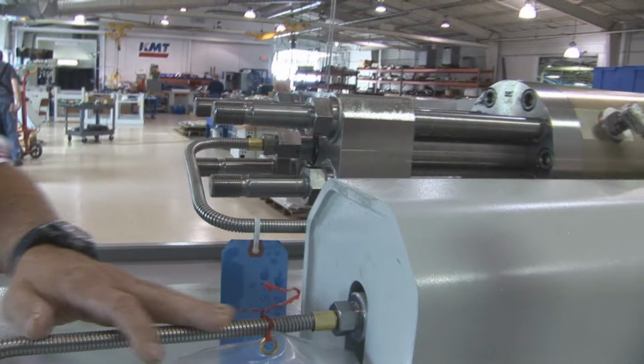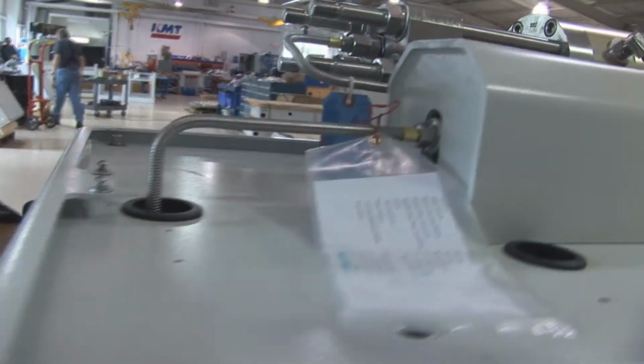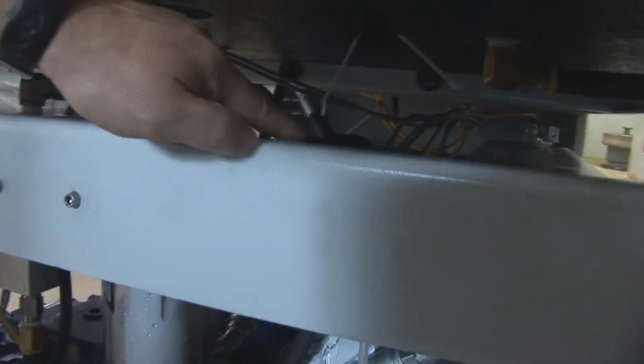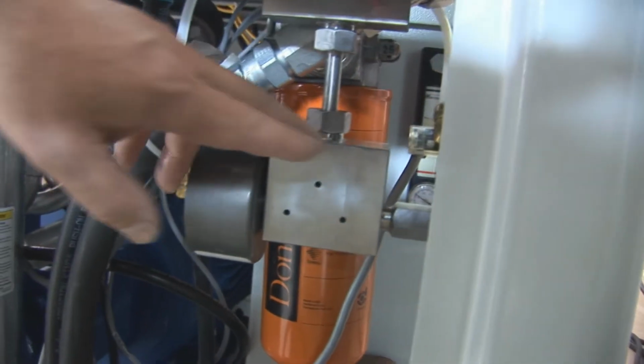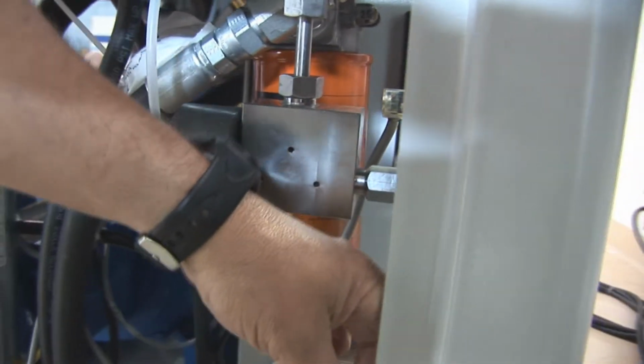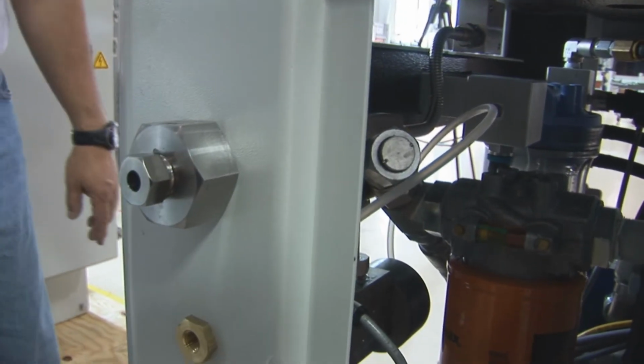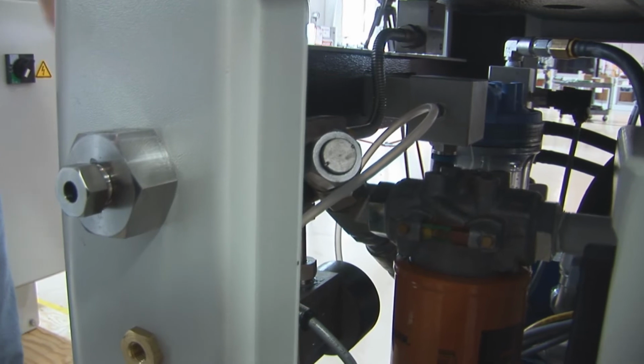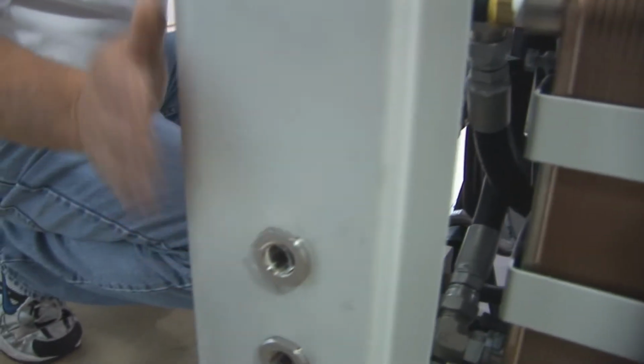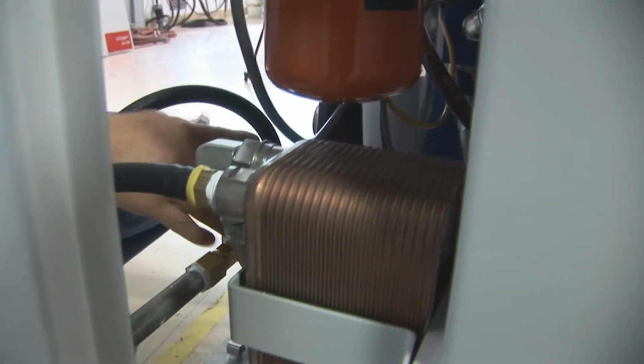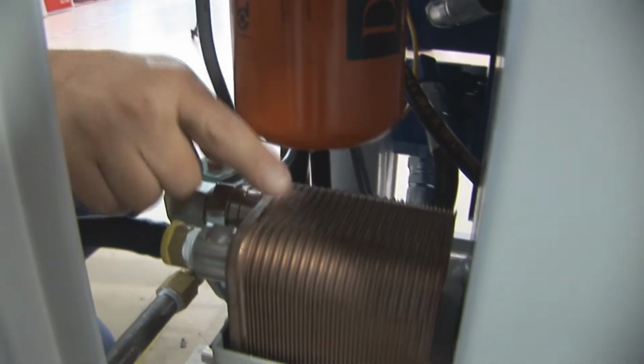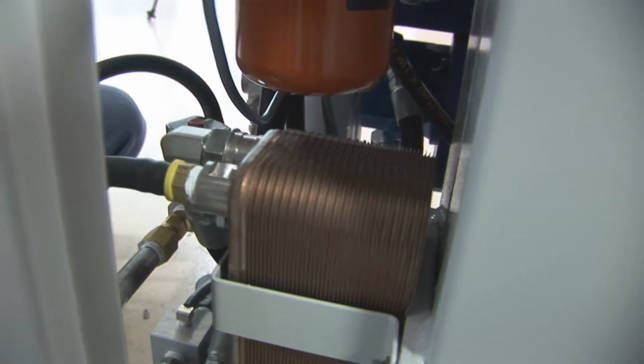From the discharge line, we come out, we go down to the dump valve. When you hit the emergency dump, emergency stop, the dump valve will open up and allow water to flow out to the drain. This is your high pressure port where it comes out, goes out to your work cell. On the cooling water side, our water comes in through this port right here, through a valve, goes into our heat exchanger, and out to the drain.